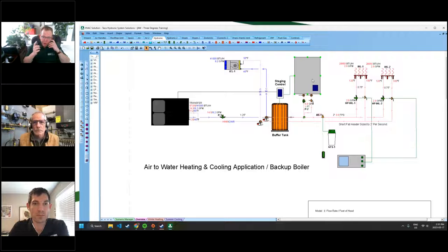Now, there's a reason I have it on the secondary side of the system: in my own application, we have time of use rates. I want to make sure that I can charge this buffer tank off peak. I don't want the boiler charging my buffer tank. I want to utilize the lowest possible fuel costs to charge that buffer tank. But again, this is my scenario. There are certainly scenarios where Bob or Max or others would go, this is not my scenario. This is not what I need. But this is a pretty typical control strategy we've done for the better part of a decade that works very, very well. Another way that we can do it is right here.